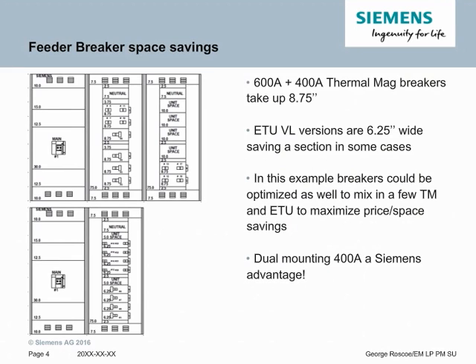One of the most common questions asked in switchboard design is, how can I reduce the number of sections? The image on the left shows one way to reduce a section. Both images have the same number of 400 and 600 amp circuit breakers. The top image uses Sentron thermomagnetic circuit breakers. Thermomagnetic circuit breakers are the most cost-effective option and are among the most frequently used circuit breakers in switchboards. One downside of these thermomagnetic circuit breakers is that they are sometimes larger than their electronic trip counterparts, specifically at 400 and 600 amps. One way to save a section in certain applications is to swap out the thermomagnetic circuit breakers for the VL electronic trip circuit breakers to see if a section can be saved. The savings per breaker in unit space is 2.5 inches going from thermomagnetic to electronic trip, which can add up quickly.